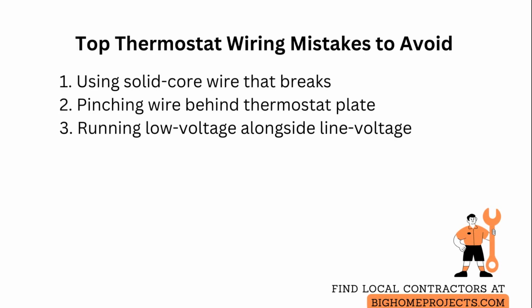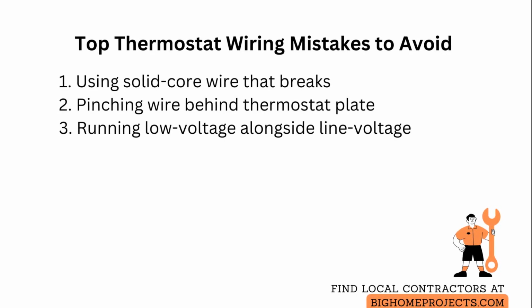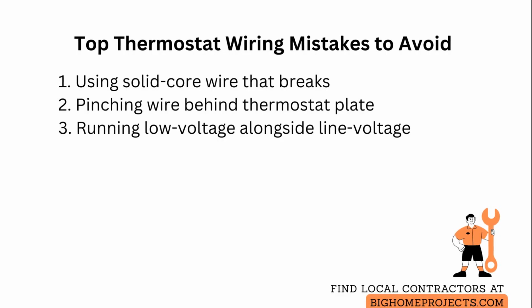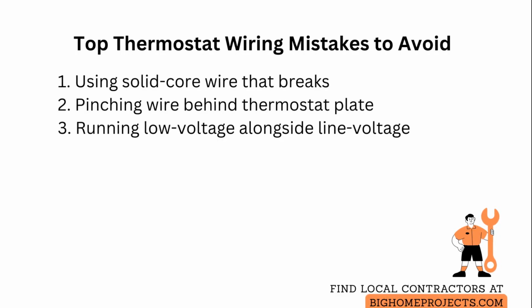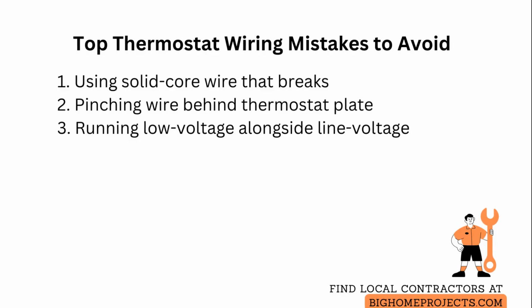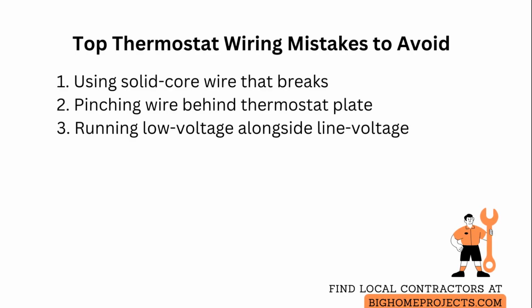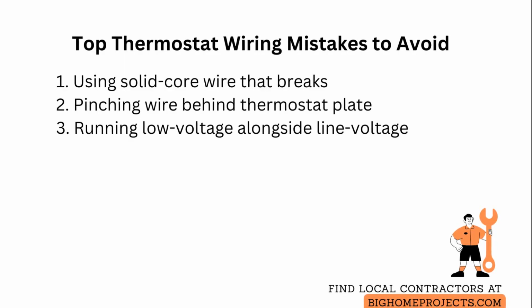Reroute and provide strain relief at the thermostat and at the control board so the jacket does not get pinched when the thermostat is mounted. Separate low voltage and line voltage runs or add grounded metal conduit between them to eliminate interaction and interference.